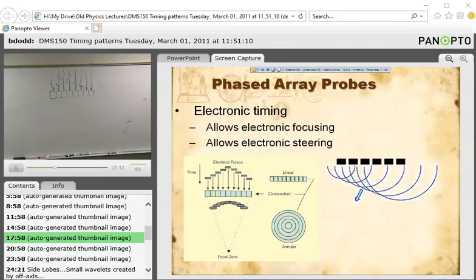What you have to do is send out two separate signals. Okay, so you send out one pulse that's focused here. So I send out one scan line that is focused right there. And then I send out another scan line steered in the same direction that is focused down here. Okay, so it requires two pulses to get two scan lines. So every time I add a focal zone, I'm adding another pulse to my image.